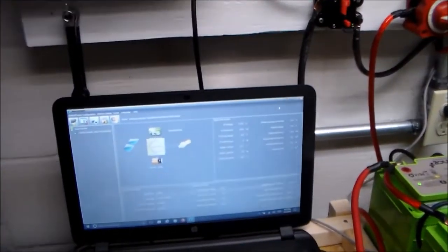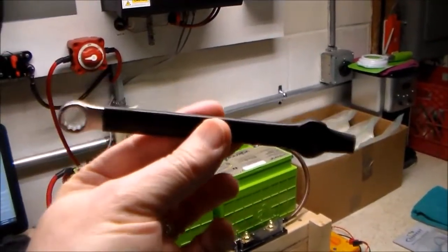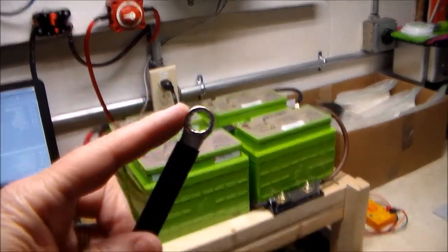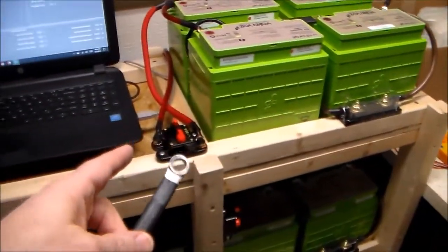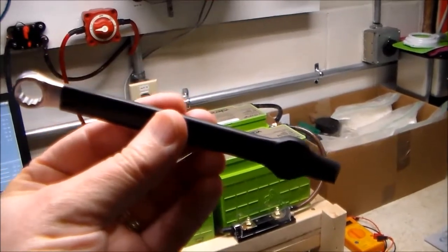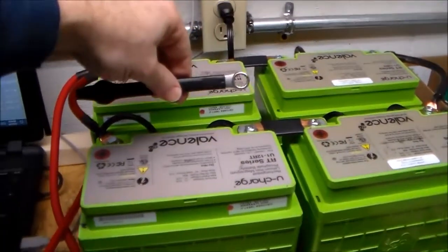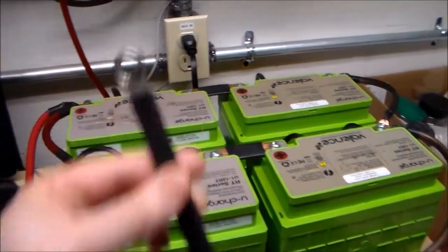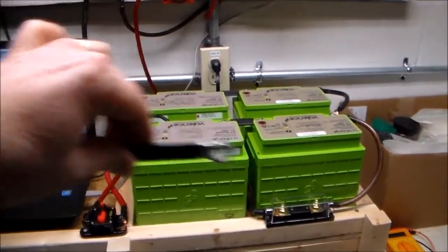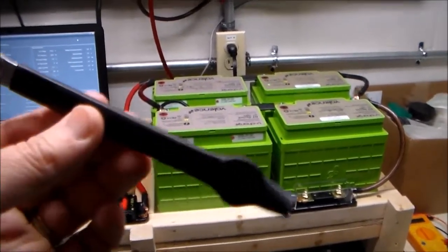And then another thing I'd like to just throw out there. If you are going to be working around batteries a lot, take the time to get yourself a wrench that's going to be dedicated to the batteries. And this is the end I'll use for tightening all my connections on the batteries, on the fuses, and on my switch breakers. But I took the time to put heat shrink tubing and shrink that. This way, if I'm working on one of the batteries and the wrench slips out of my hand, there's no way for me to short circuit between the two battery posts. I've seen that done before, I've actually done that myself before and had a wrench like this welded between two battery posts. And it's something that can be very dangerous and can actually take your life.